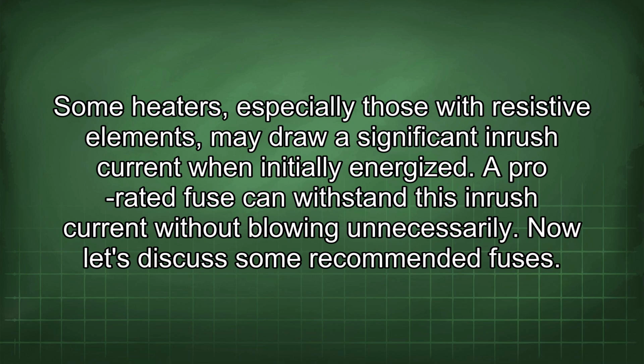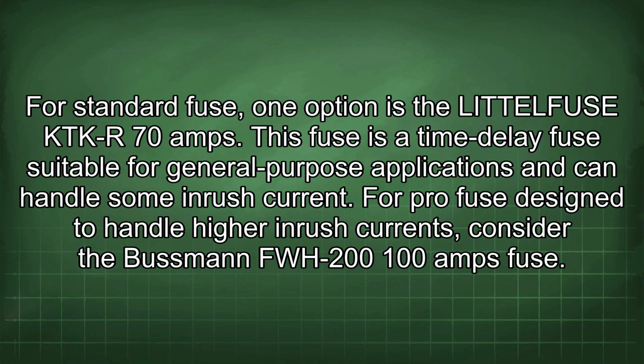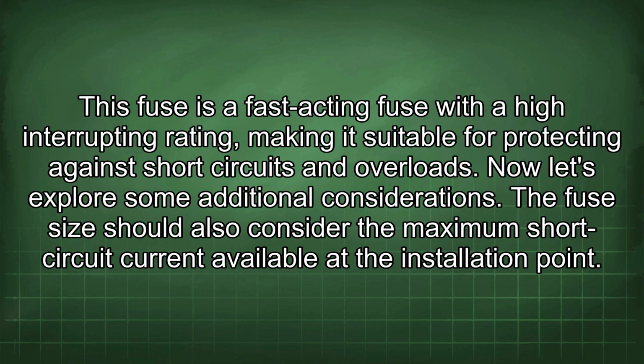Now let's discuss some recommended fuses. For a standard fuse, one option is the Littelfuse KTKR 70 amp. This fuse is a time delay fuse suitable for general purpose applications and can handle some inrush current. For a pro fuse designed to handle higher inrush currents, consider the Bussmann FWH-200 100 amp fuse. This fuse is a fast-acting fuse with a high interrupting rating, making it suitable for protecting against short circuits and overloads. Now let's explore some additional considerations.